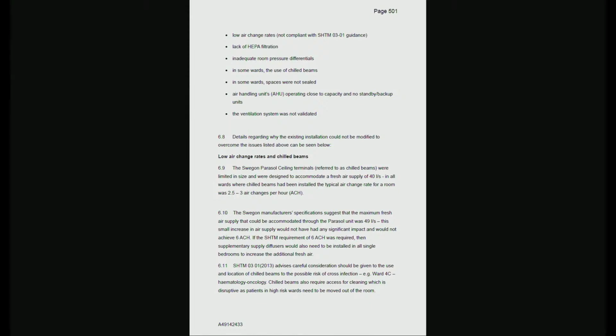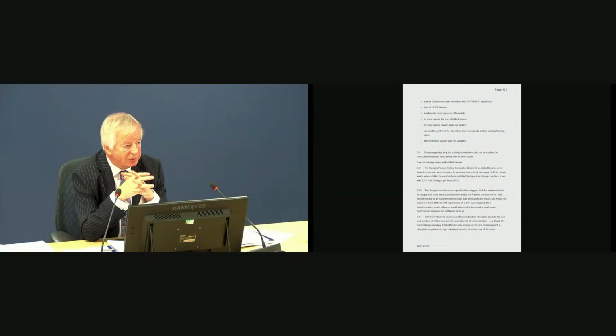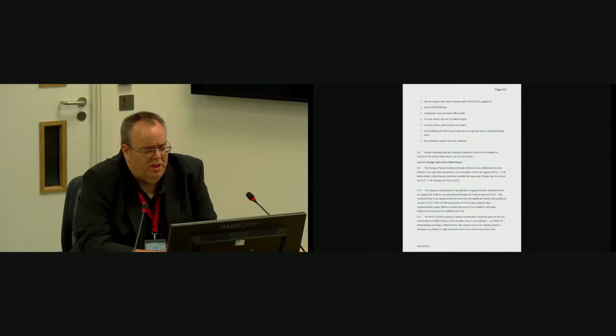I suppose if one thinks about it, does something depend on how often you think you might have to clean them as to whether they're appropriate for a patient room? Yes, and chilled beams require a relatively high level of maintenance, and that maintenance may well have to be carried out with the patient present. So you are introducing further sources of contamination by the maintenance activity. But it also is fundamentally linked to the total air change rate where a chilled beam will function, and that is lower than the minimum air change rates specified within SHTM.